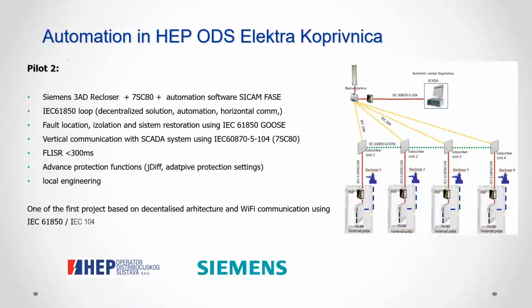Also, the system has new protection functions such as jDiff. That's a new protection function that came with the second phase automation software, and with it they can locate and isolate the fault in the system. And we also use adaptive protection settings for the relays. So when the system finds the fault, isolates it and reconfigures, the protection relays get new settings for the new grid after the fault. That's the first project based on decentralized architecture and on Wi-Fi communication.